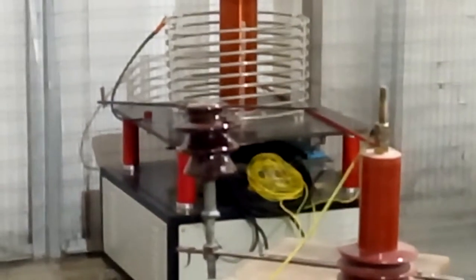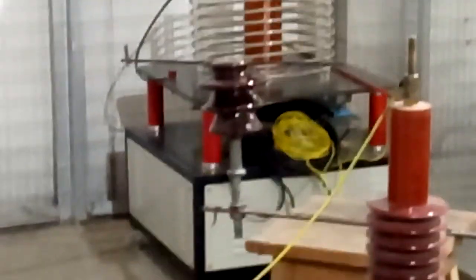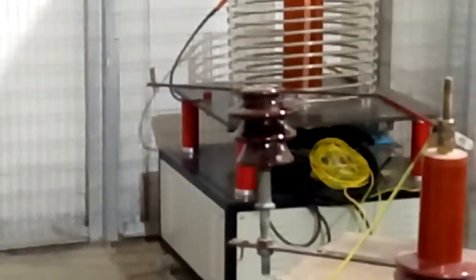Now see, all the spark gaps have triggered but the insulator has sustained this voltage. There was no flashover across the insulator.